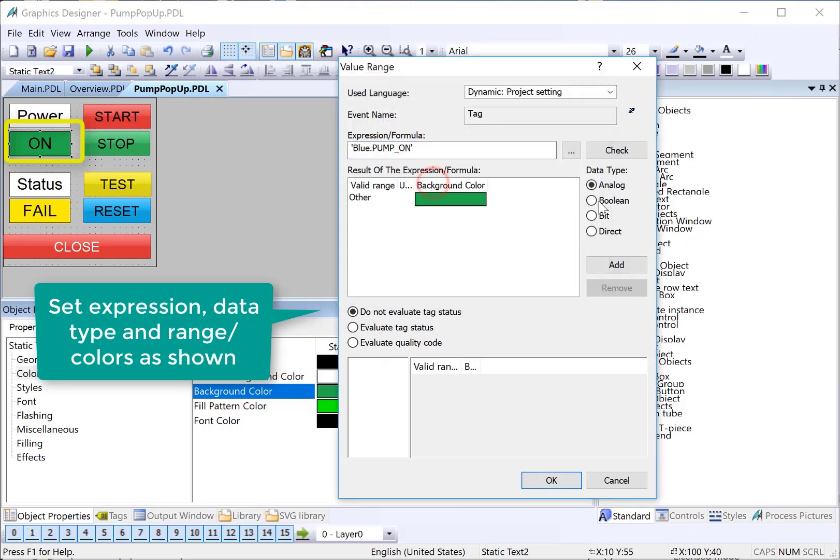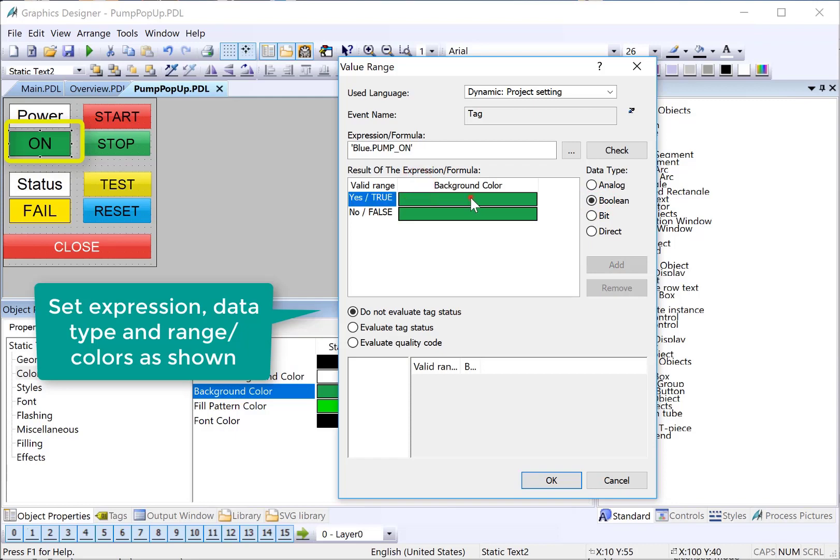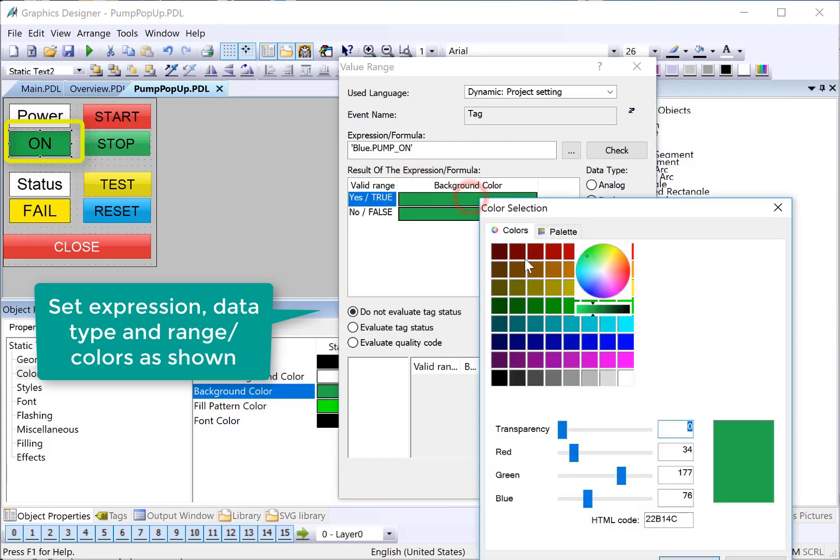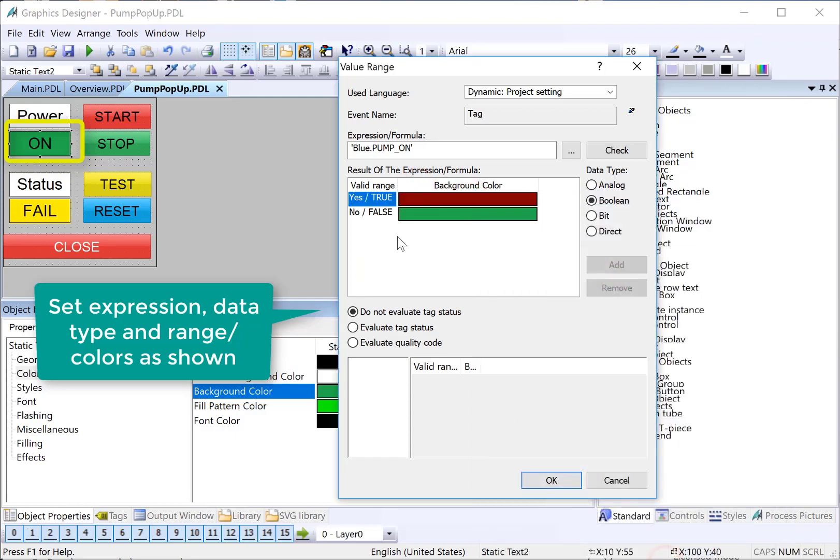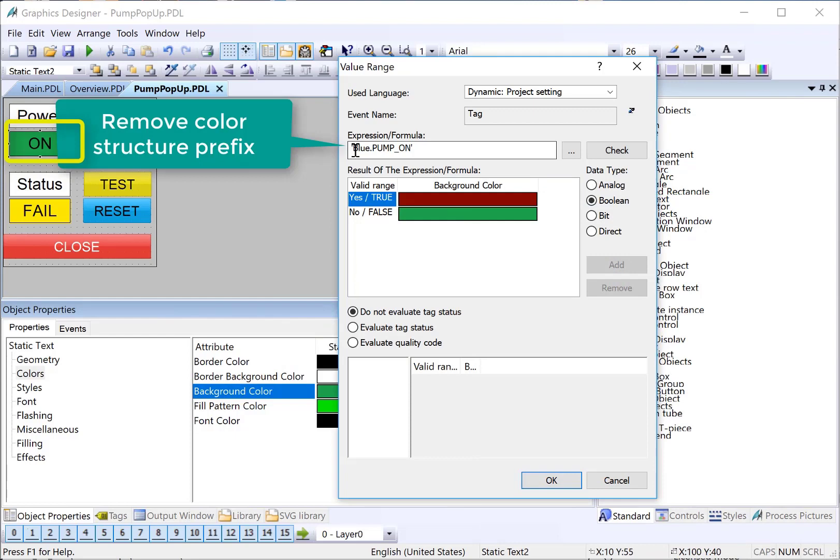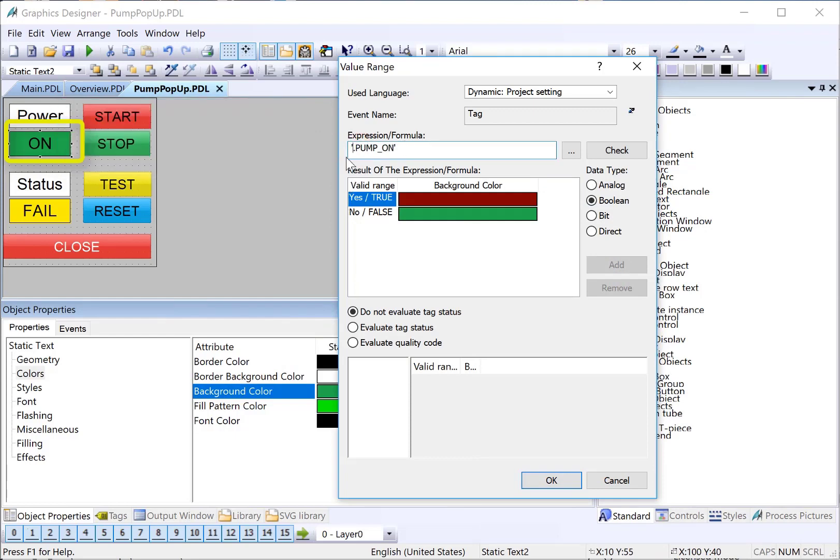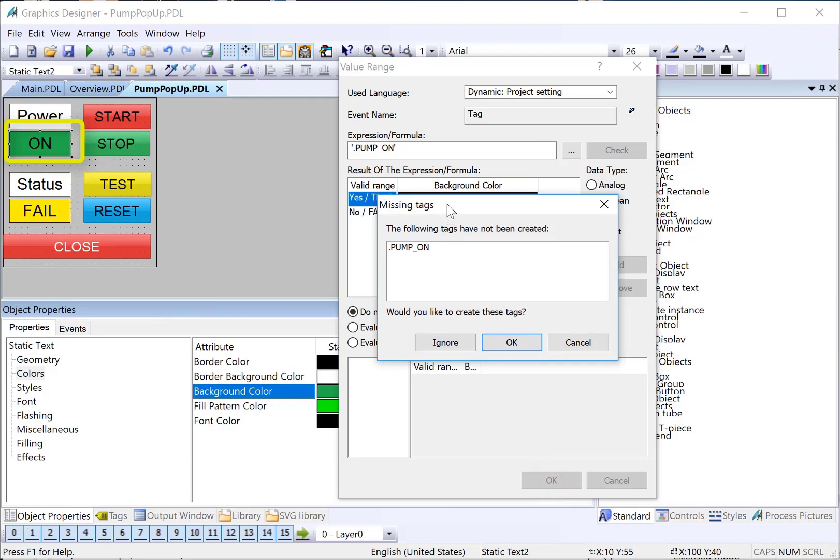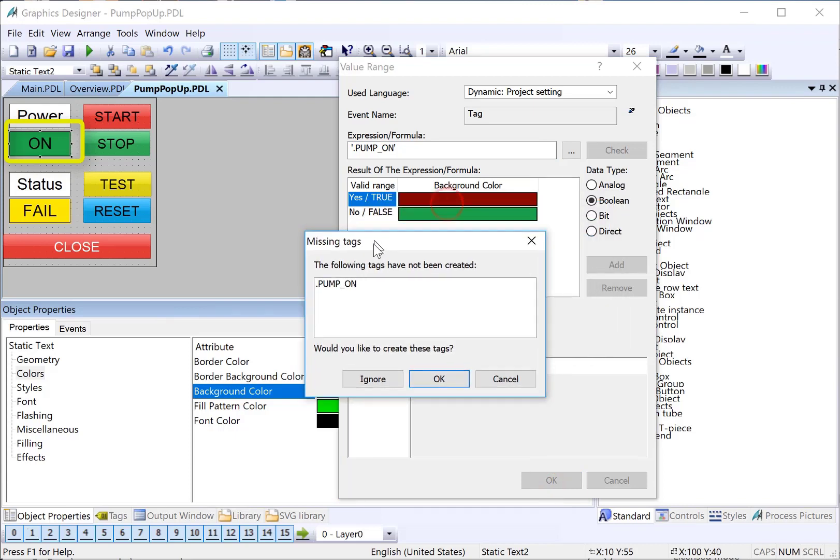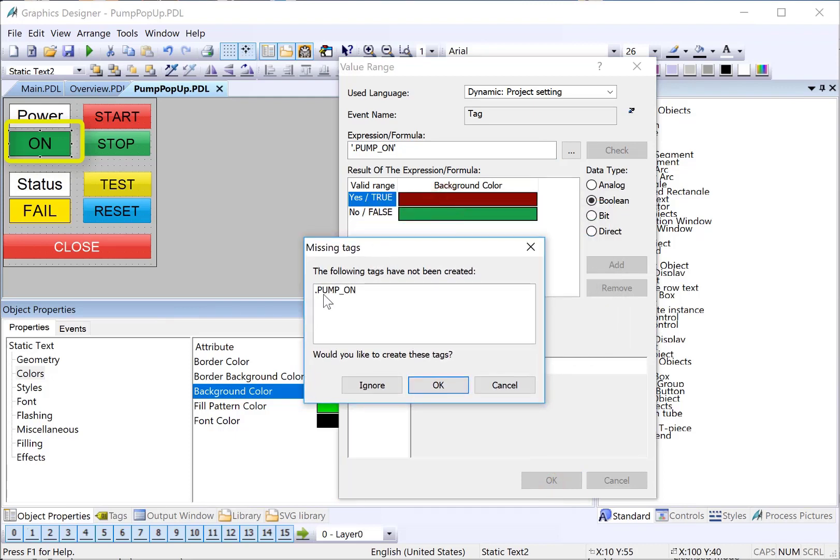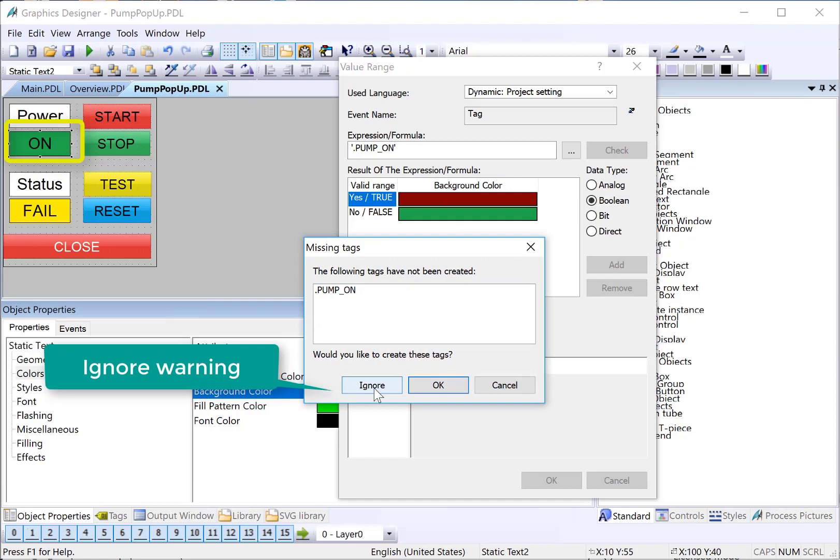We'll add a Boolean expression. If the pump is on, background color is red. If it's off, it's green. And we're going to get rid of the prefix and only use the member name, which starts with a dot. In this case, dot pump on. Now, when we do this and click OK, it's going to try to be helpful and say, hey, this tag doesn't exist. You're just going to click ignore.